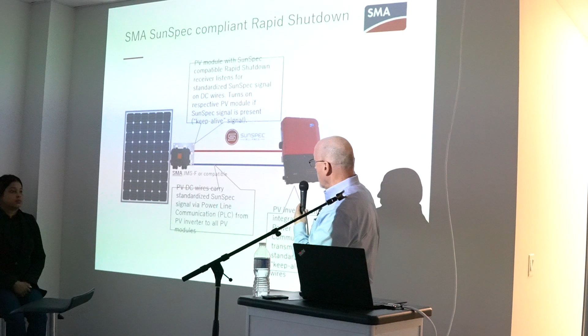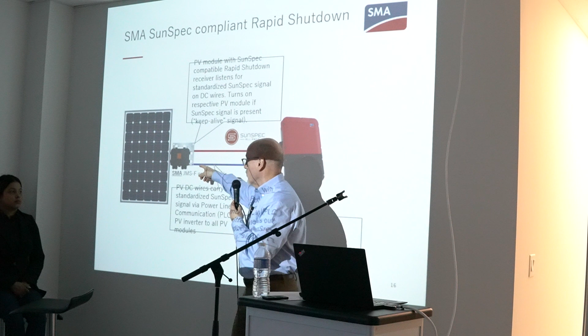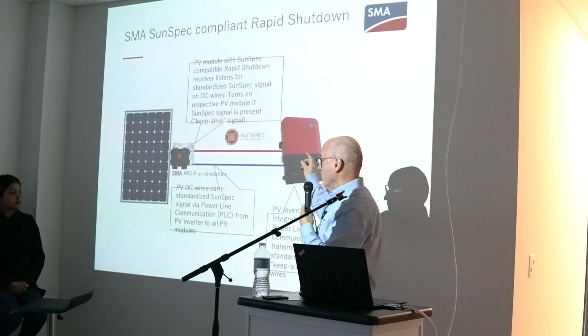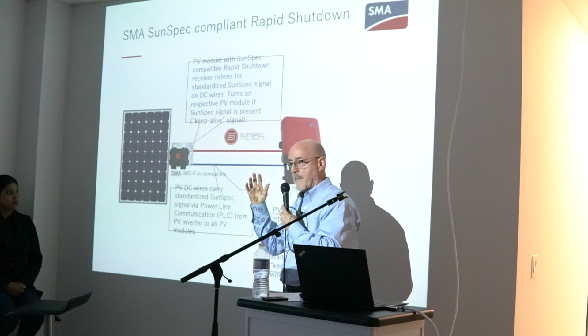As long as there's AC power, that keep-alive signal is sent to what's referred to as a SunSpec receiver, which is listening all the time. As long as that signal's there, it keeps the DC conductors connected. Once the AC power is lost or the AC disconnect is flipped, the signal goes away, the receiver recognizes it and goes into a rapid shutdown mode in an NEC, National Electric Code compliant fashion.